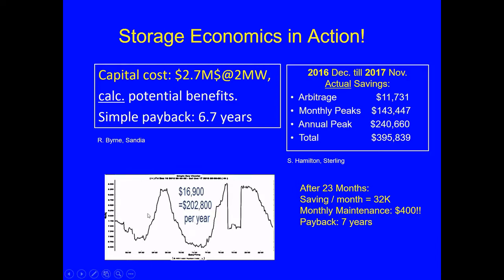This is how it works. This is the way the daily variation goes, and then when the monthly peak occurs, the storage kicks in. A single storage event saved $16,900, multiplied by 12, and you get $200,000 per year. Taking together the last 23 months of operation, the savings per month were $32,000. Interestingly, the monthly maintenance was only $400 - not $1 million, not 1,000 hours, but $400. Again, the payback on the actual savings ended up as 7 years.